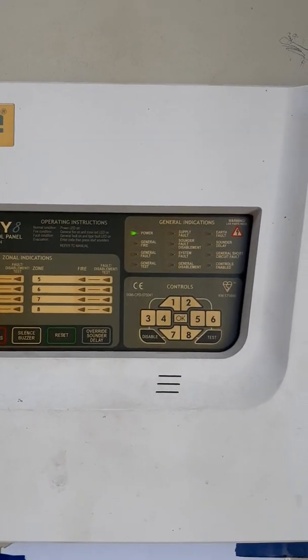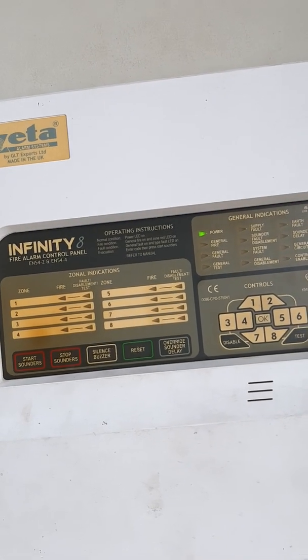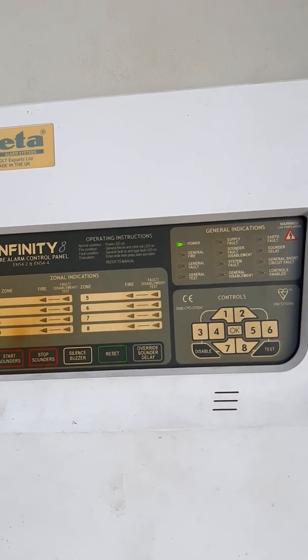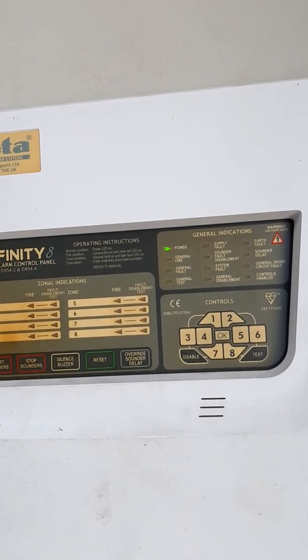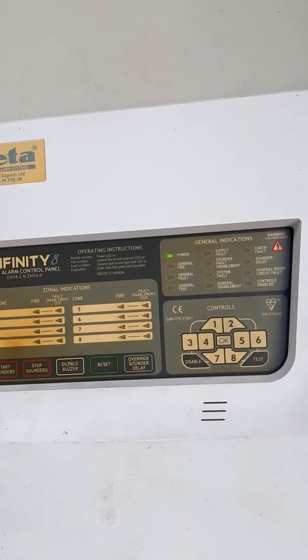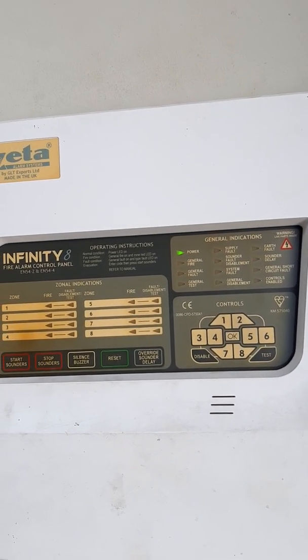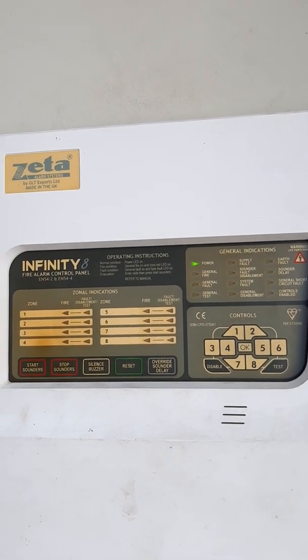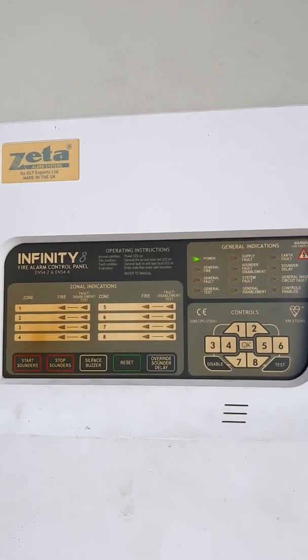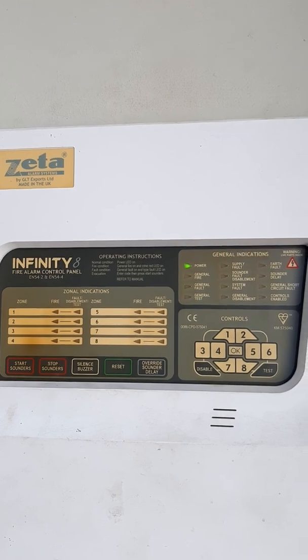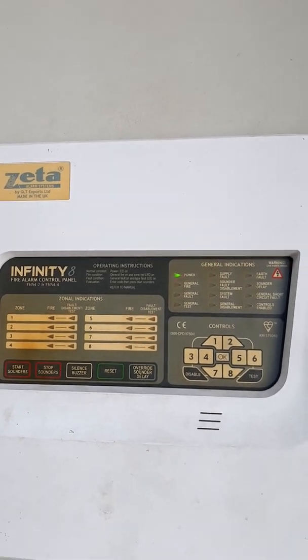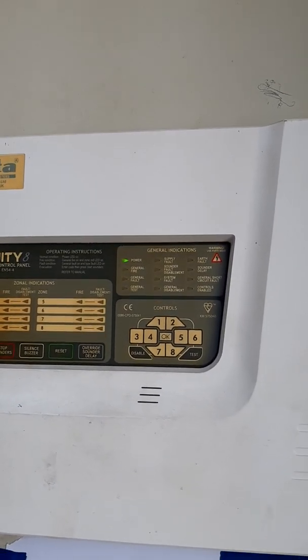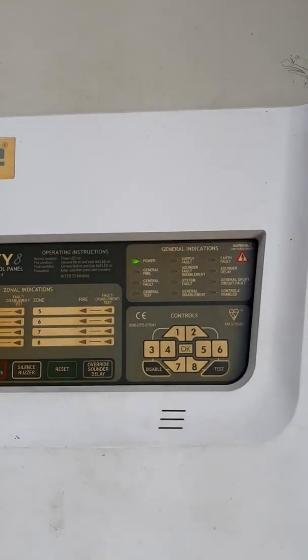The second fault is sounder fault. If the sounder fault indicator light is blinking, you check the bell zone circuit wiring, check the bell connection, and manually check the bell with a 24V DC power supply.